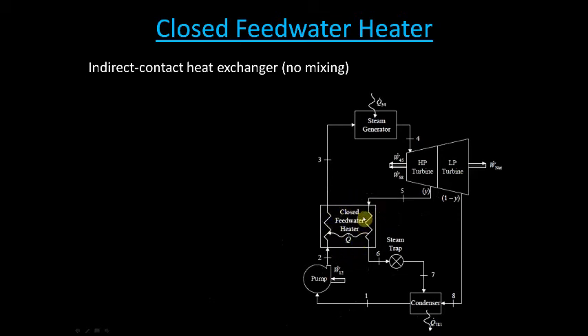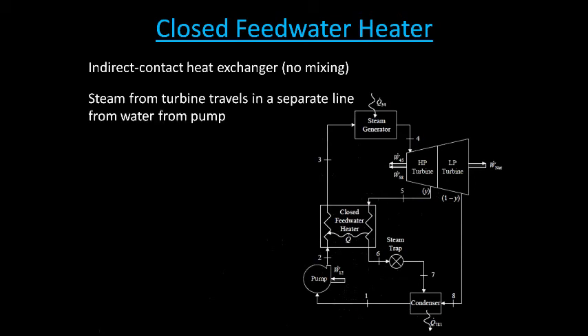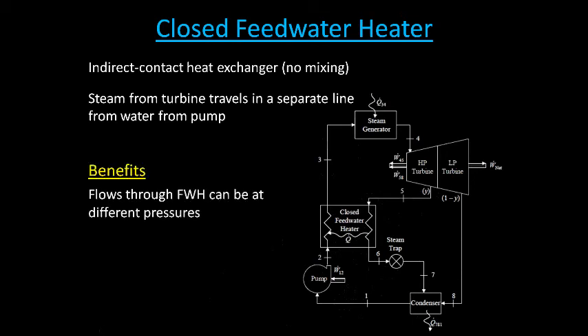In this case, we're talking about a feed water heater, so the purpose of this heat exchanger is to heat the fluid before it goes into the steam generator. So the steam comes from the turbine and travels in a separate line, still coming from the turbine, but traveling in a separate line to heat the water from the pump. Now, the main benefit of this over the open is that the flows going through it don't actually mix, so they can have different pressures. We don't have to have a second pump installed.